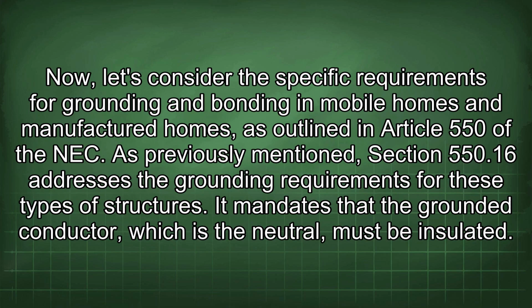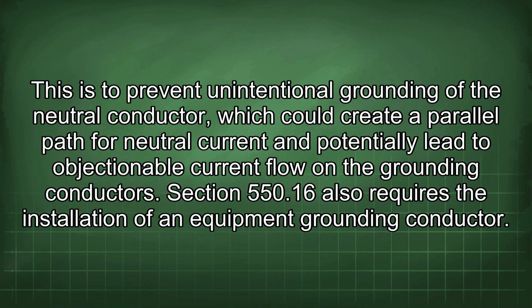Now, let's consider the specific requirements for grounding and bonding in mobile homes and manufactured homes, as outlined in Article 550 of the NEC. As previously mentioned, Section 550.16 addresses the grounding requirements for these types of structures. It mandates that the grounded conductor, which is the neutral, must be insulated. This is to prevent unintentional grounding of the neutral conductor, which could create a parallel path for neutral current and potentially lead to objectionable current flow on the grounding conductors.